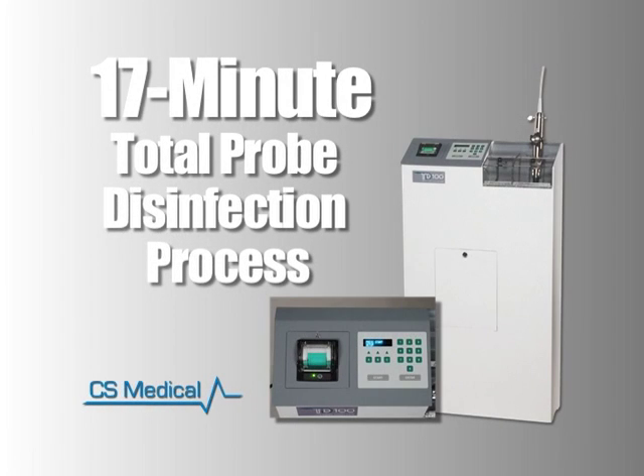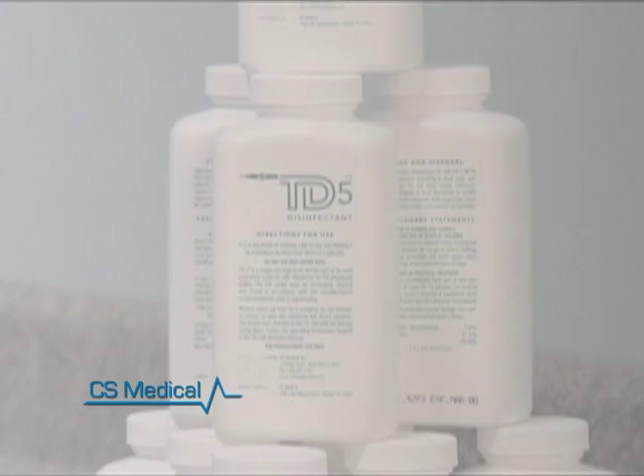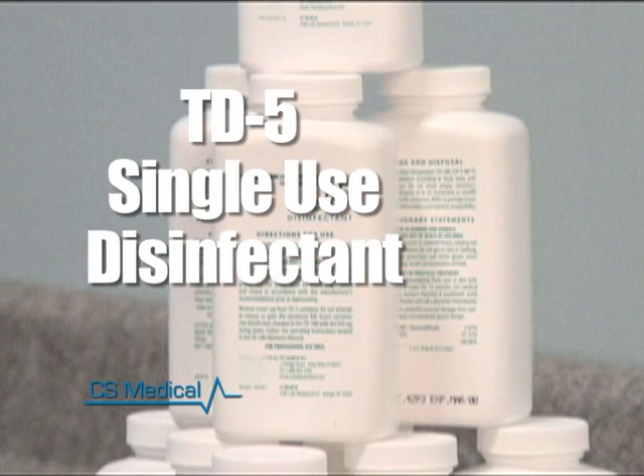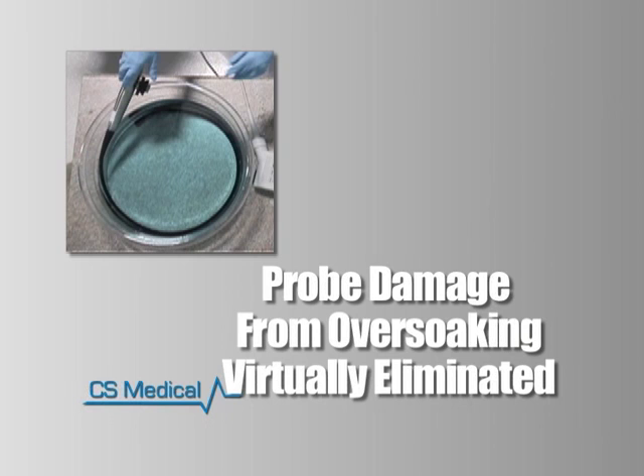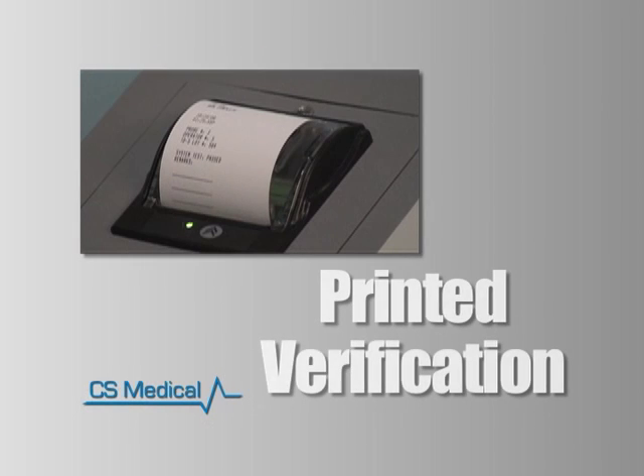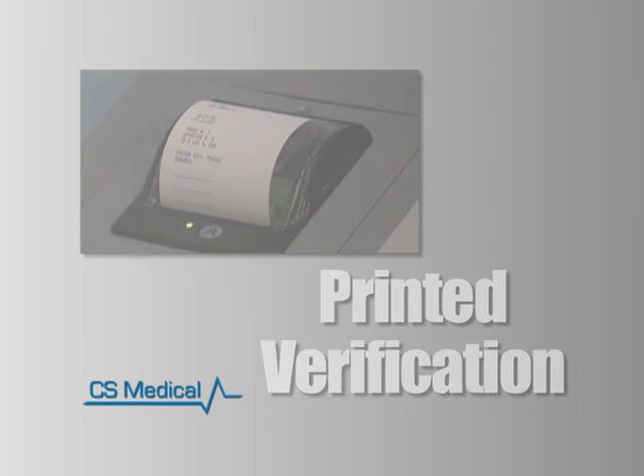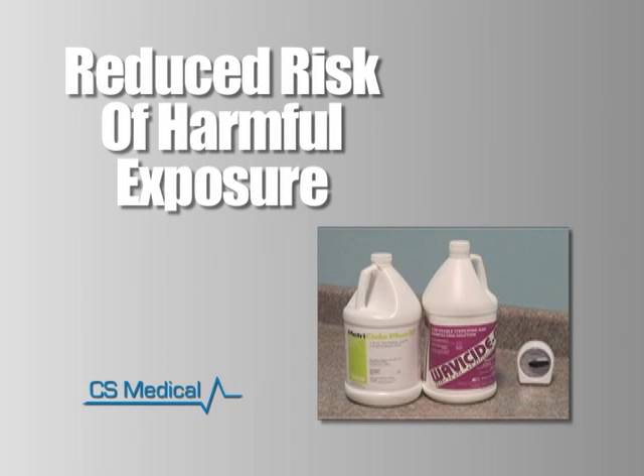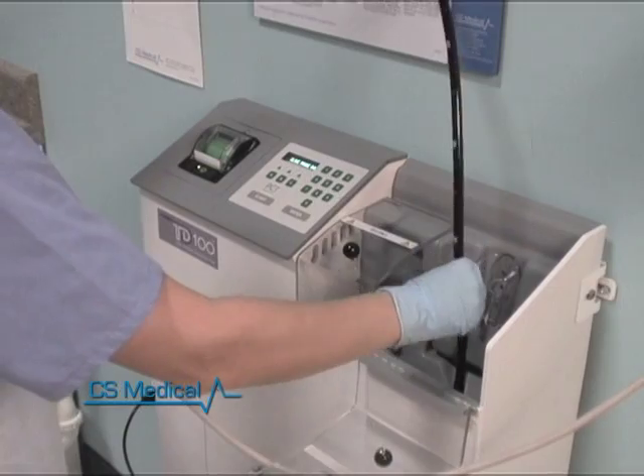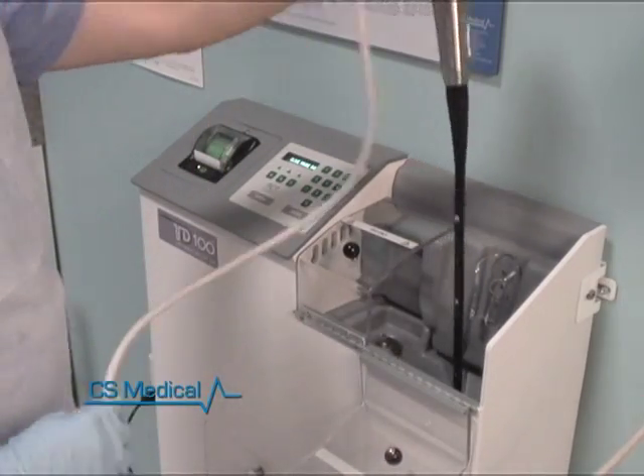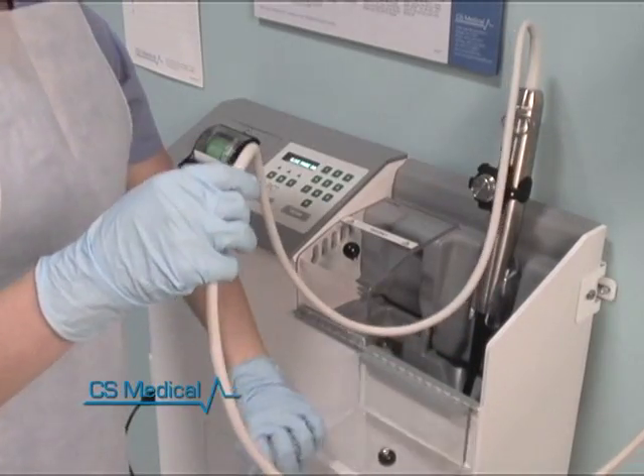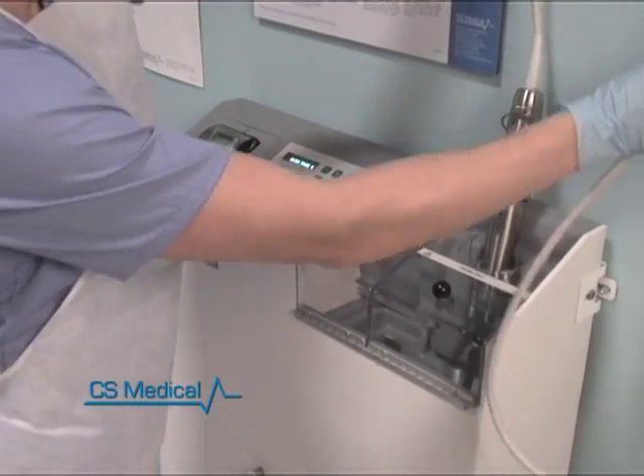The TD100 offers you a 17-minute disinfection cycle where the probe remains stationary, thus minimizing probe damage. Single-use TD5 high-level disinfectant to effectively kill microorganisms. Probe damage resulting from over-soaking is virtually eliminated. Printed verification record of completed TEE probe disinfection. Reduces risk of exposure to harmful high-level disinfection agents. The TD100 Automated Transesophageal Probe Disinfector allows you to disinfect delicate TEE probes with the confidence that each and every TEE probe will receive the same validated disinfection process.